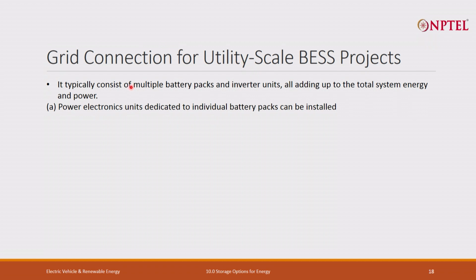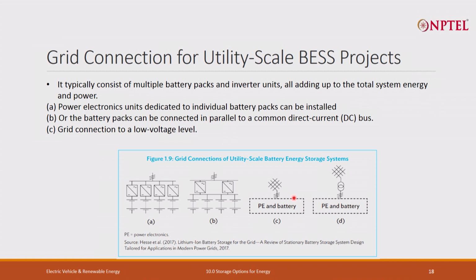Grid connection for utility scale mostly consists of multiple battery banks, like multiple containers placed at one place, and that all adds up to the total energy storage and power. Then you have power electronics to individual as well as combined battery packs, or these battery packs can be combined in parallel to a common DC bus with electronics taking and giving power from that DC bus. So either you can have individual units, or combine all units together and provide the converter system as a whole, or have a power conversion or conditioning system at each unit. That depends upon the cost, capital investment and the requirement of that particular place. Both architectures are being used in the industry.